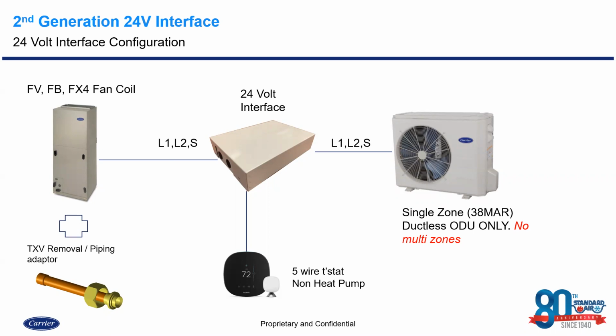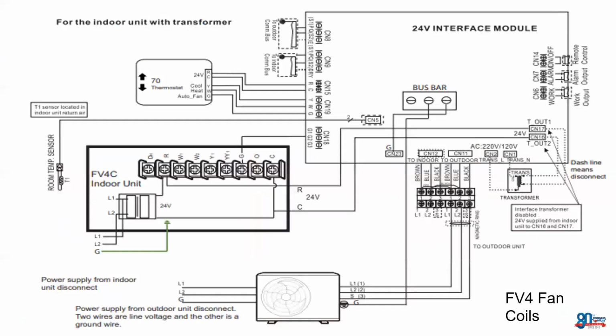And then, of course, because we have a hybrid combination, we have an EXV at our ductless outdoor unit, so we need our TXV removal and piping adapter, which essentially is a male Chatleff fitting that removes the TXV from that indoor unit so that we don't have a double pressure drop. In essence, this is what we need to make this FV, FB, and FX hybrid combination possible. So let's take a look at what we need to actually make it work wiring-wise.